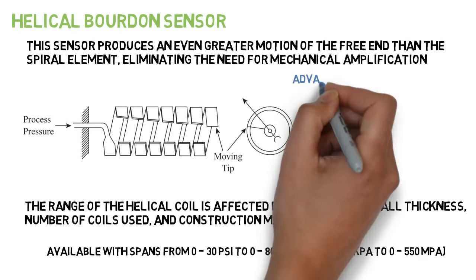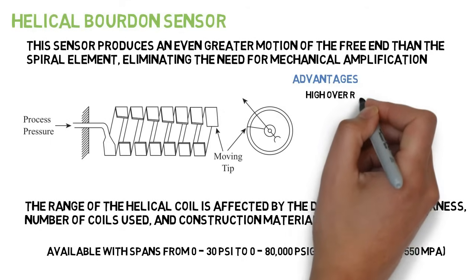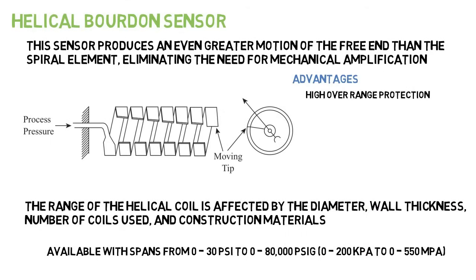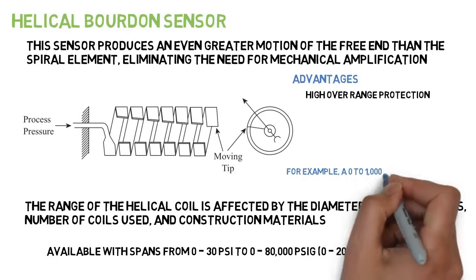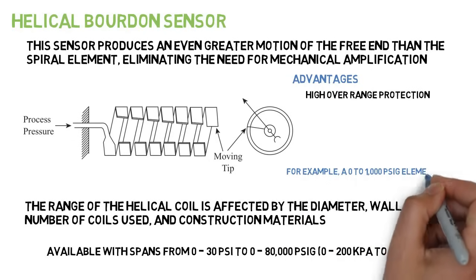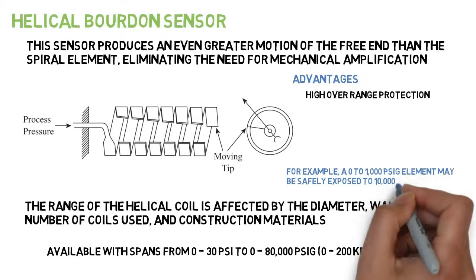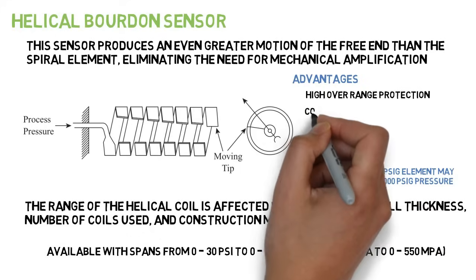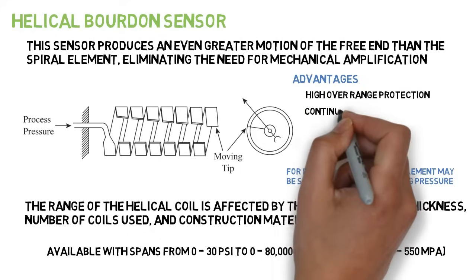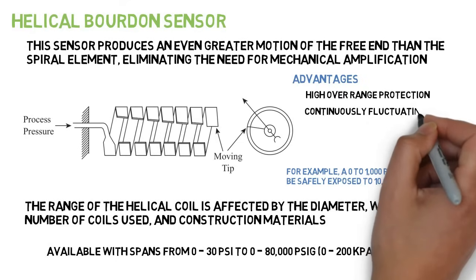Other advantages of this design include high over-range protection. For example, a 0 to 1,000 psi element may be safely exposed to 10,000 psi pressure, and it is suitable for pressure measurement on continuously fluctuating services.